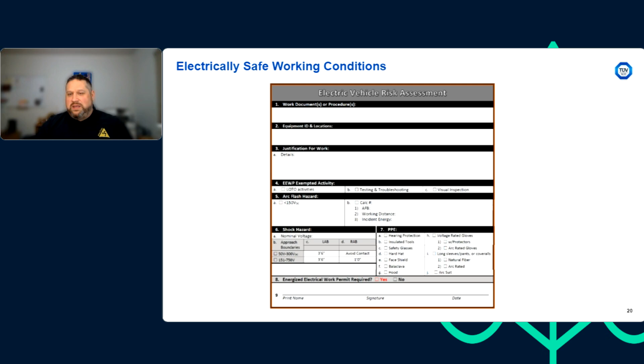We always have to account for human error as well. This was a big thing emphasized in NFPA 70E, that we're going to make mistakes, to the point where it's predictable. So if we have a significant task that, if done wrong, could cause injury to a person or to the equipment, we can take additional steps and precautions to help minimize the chance of human error occurring. That would be things like having written work instructions, performing a pre-job brief, or having a second person there to validate that we're doing the right steps. Those are easy things for us to incorporate as part of our processes.